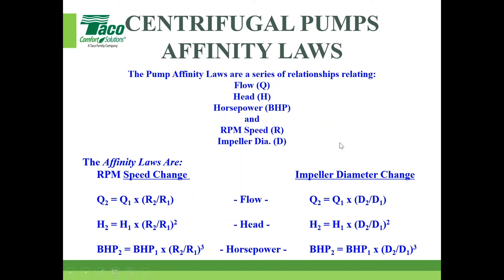Yep. So one of the basic fundamental pages. It's really not that fundamental, but it is once you start looking at the formulas, is these centrifugal pump affinity laws. It's really the relationship between flow, head and horsepower, and you can see impeller diameters or impeller speeds. We pump manufacturers use it. It's embedded in our programming to calculate what size to trim the impeller. Every time we get a flow and head calculation, we need to trim that impeller, so somewhere there's a calculation that follows this.